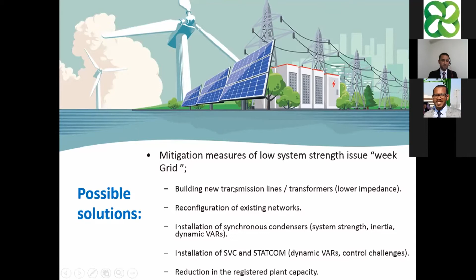The last one, of course, is to reduce the registered plant capacity, and this is maybe the last thing we want to do. So if we have a plant registered with 100 megawatt solar, we might ask them to limit the dispatch output power from 100 to 80, for example. This is one of the solutions to mitigate the low short circuit ratio in the network.